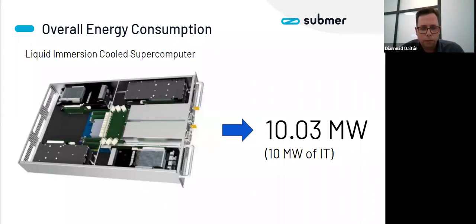The main difference is there's no piping, the chassis is much simpler, and there are no components used to support air handling or air cooling in the node. So essentially you see a much cleaner environment or footprint, leading to no moving parts. By using immersion cooling to cool these nodes, we reduce drastically the amount of cooling capacity required versus IT - for these 10 megawatts, we only really need 30 kilowatts of cooling capacity. And with no moving parts, far fewer hardware failures as well.